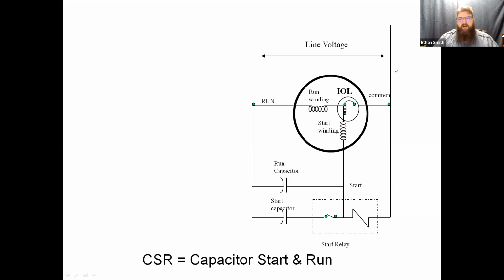So this is very common in air conditioners. This could be an air conditioning compressor. You've got your run capacitor that we're always used to seeing, but a lot of times you'll see a start assist capacitor on there as well. And it comes with a little box attached to it that we call the start relay. So these start relays are kind of fun. This little symbol right here is the coil of the relay. What you'll notice is the voltage rating on that start relay is very close or similar to the voltage rating on your capacitor.